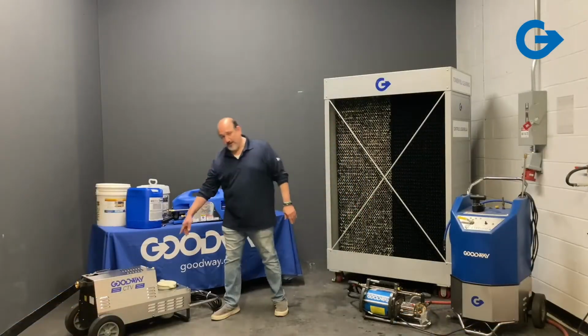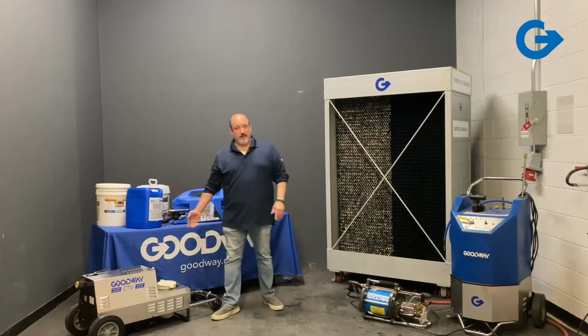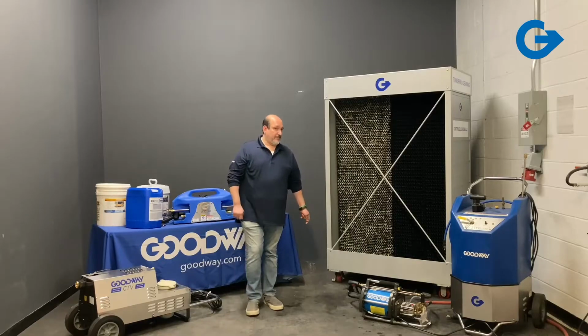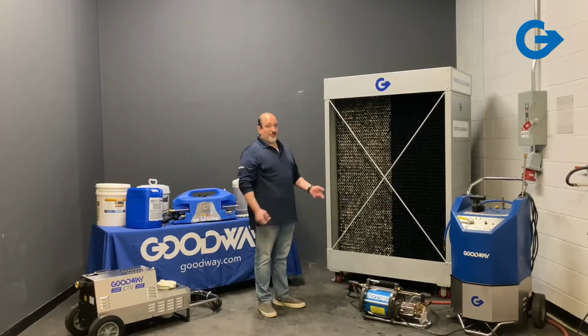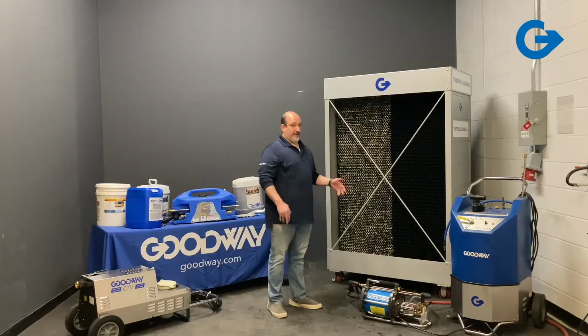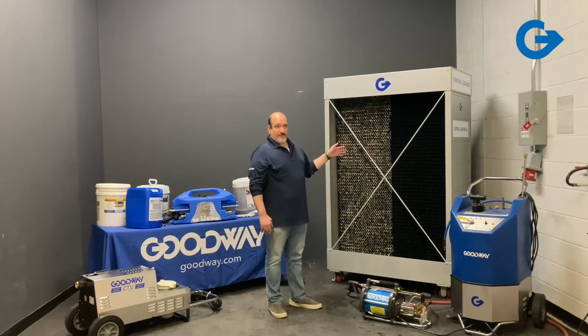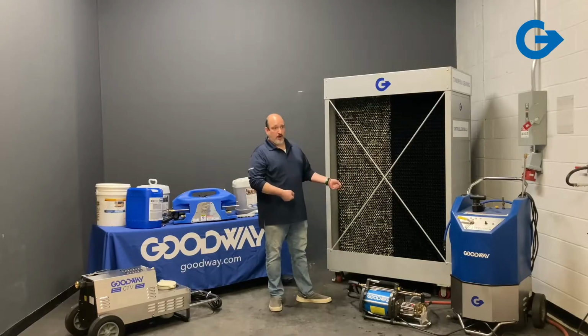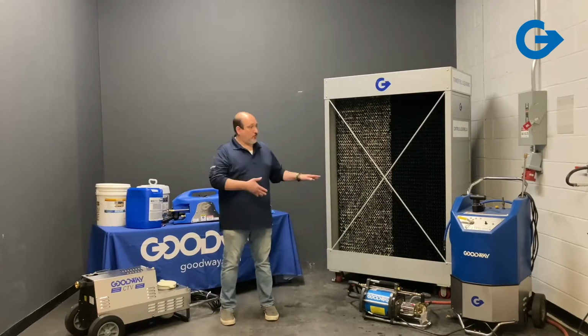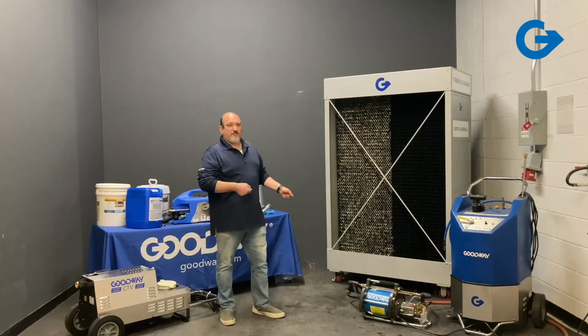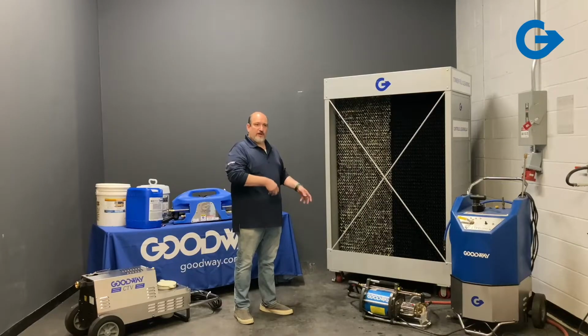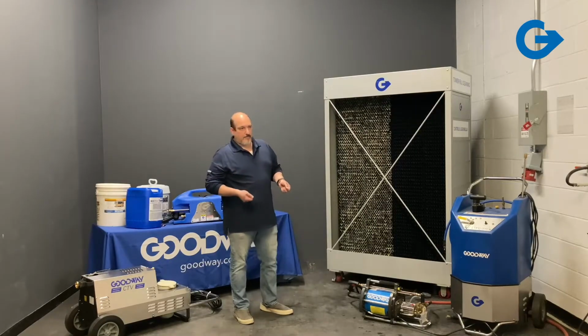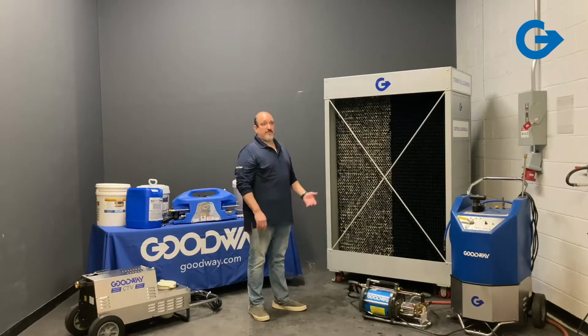So we have a few different machines and a few different chemicals. I'll start over here with our cooling tower vacuum. This was the first machine we introduced for cleaning cooling towers, and it's used for cleaning the basin. What's nice about it, besides getting all the sediment out of your tower, is that you can use it online, so you don't have to shut down your towers for a whole weekend and drain everything out. You can turn the fan off for about an hour, go in with a wand and different tools, and vacuum out all the sediment in the tower, almost like vacuuming a pool, going slowly so you're not picking up the water and making it cloudy, but quick enough to get through a good size 750-ton tower in less than an hour.